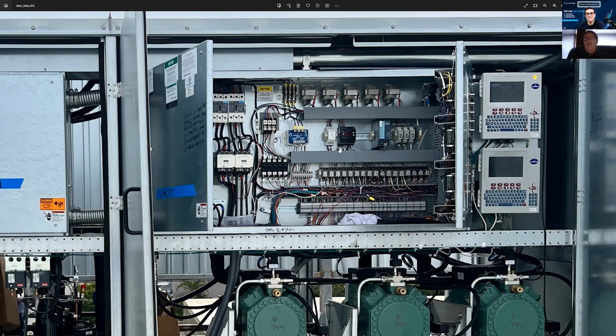Check your voltage there. Your voltage is going to be anywhere from 3 to 5 volts. If it's 3 to 5 volts on the left, it needs to be 3 to 5 volts on the right. If they're not, the 326A operates off a holding value. It constantly has voltage on the gas bypass valve. So if you lose voltage on one side, it's always going to creep in that direction, because now they're not both 5 volts. One's 5, one's 4.5. It's going to start creeping to the closed side. So if those values are not correct, you've got a problem with your 326A.